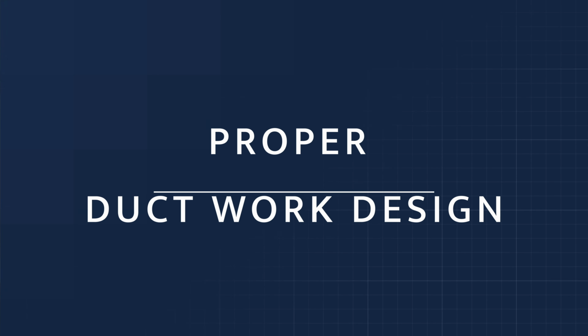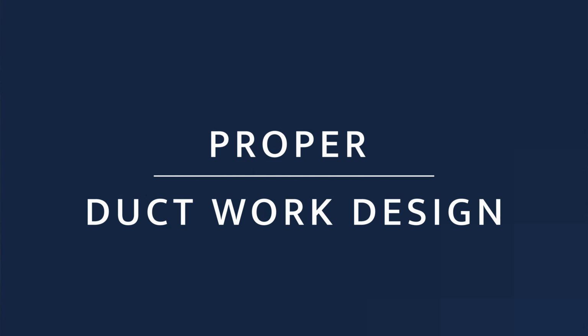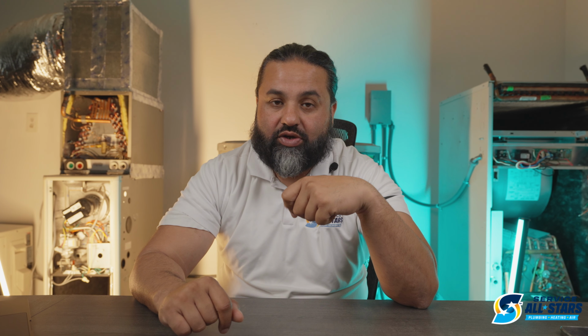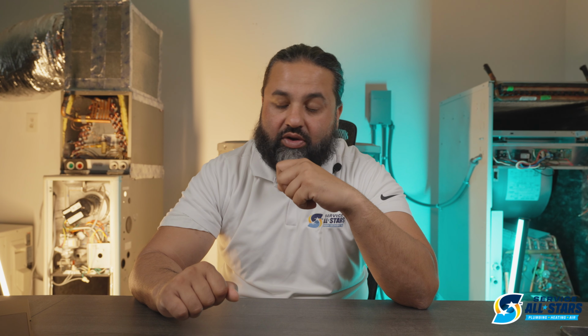What I want to go into next is proper ductwork design. Proper ductwork design starts right after the air leaves the actual air handler and enters into the plenum. So the plenum has to be the correct size. A lot of times contractors will put no plenum at all because they want to save a few $100 by not doing it, and they'll attach the return duct straight to the air handler or the furnace. And same thing on the supply side. They might have a plenum, but it's a shorter plenum, or a lot of times they use these coils that are integrated with a plenum. So the plenum and the coil is actually one piece.